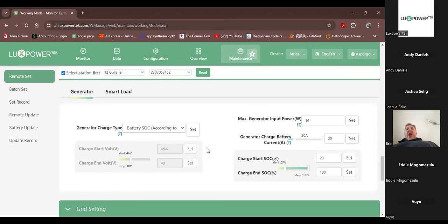Some generators, or most generators, should have a voltage regulator. But if your generator battles to keep the voltage and the frequency stable while running, then we advise you to add load on one of the generator plugs before it gets to the inverter. Maybe add like 1,000 watt or 1 kilowatt load there just to get the voltage regulator to stabilize. But the power it sends to the inverter is stable. Remember that the generator relay will only open when the voltage is stable as well as the frequency. If it cannot deliver stable voltage and frequency, then our relay will not open.